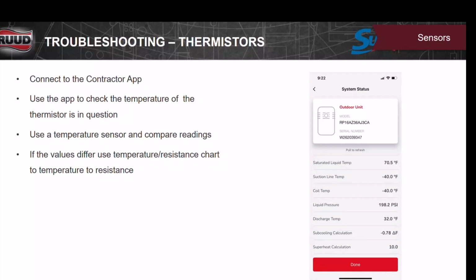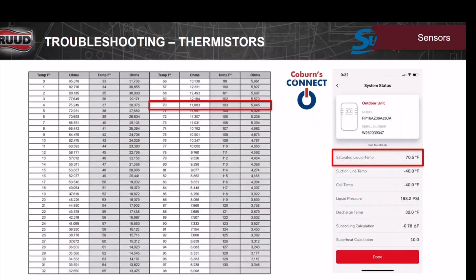The best way to check a thermistor is a cup of ice cold water, a lot of ice. Drop the thermistor down inside and you measure it. Should be at 32 degrees at that point, thereabouts. You can go to the chart that we have on the Coburn Connect app, and you can go to 32 degrees and know what you're supposed to read at 32 degrees on your ohm reading. So you check it that way. You can also put a thermometer right there where the thermistor connects onto the coil. Check that and see if it lines out to where you're at. May not be exact. It may be a little bit of ohms off, but it should be pretty dang close.